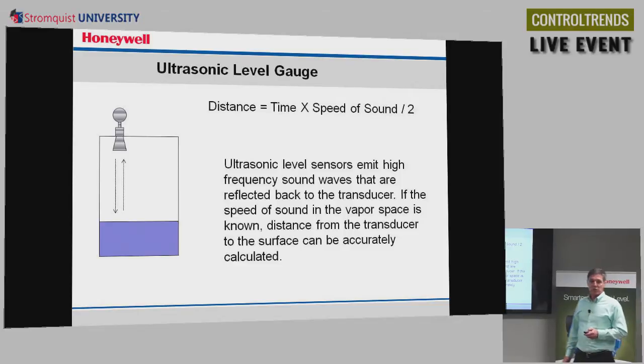The next technology is ultrasonic. For an ultrasonic level gauge, it's similar in a sense to what we've been talking about with radar, but instead of a radar signal, it's sending out a sound wave. So it's an ultrasonic sound pulse that's being emitted. That's sent out and bounced off of the surface. It comes back up. In this case, we measure how long it takes for it to bounce off the surface, and we assume the speed of sound in air, or whatever the vapor is that it's traveling through. So it has to have a medium like air to travel through. Sound will not travel in a vacuum.